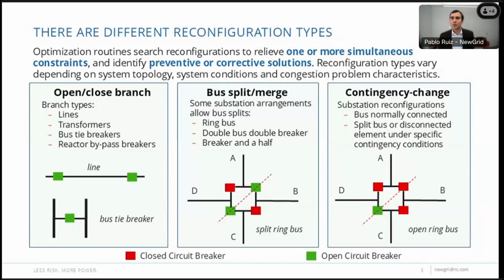There are different reconfiguration types. They could be developed for use in preventive or corrective mode—two quite distinct approaches—and may consist of one or multiple actions, such as opening or closing branches like transformers, transmission lines, or bus tie breakers, or reconfiguring substations to split or merge a bus, or pre-positioning the substation such that critical contingency impacts on the system are more benign than otherwise, while keeping pre-contingency connectivity as if the system was intact.